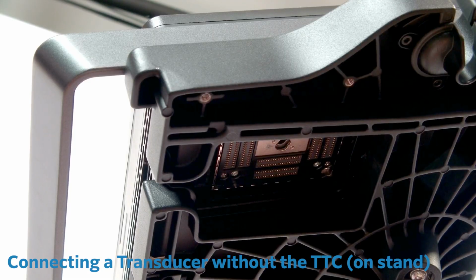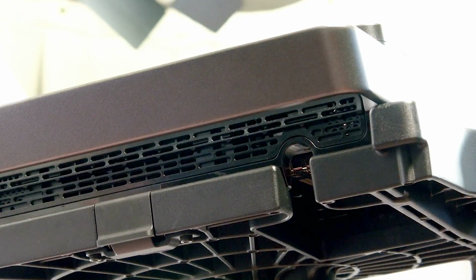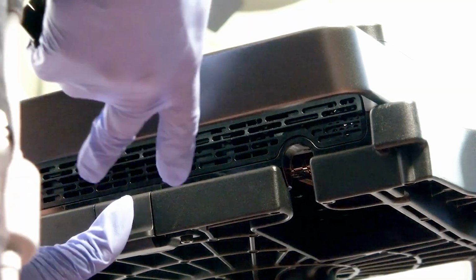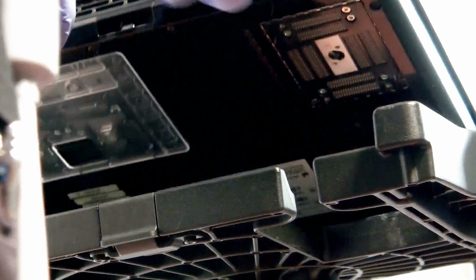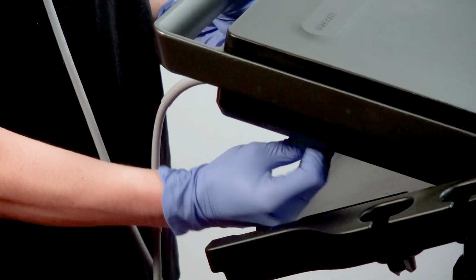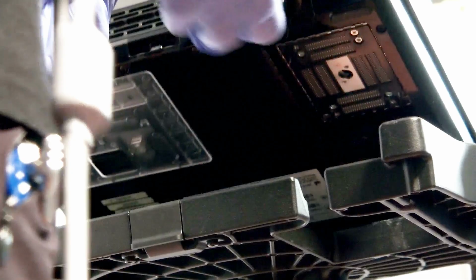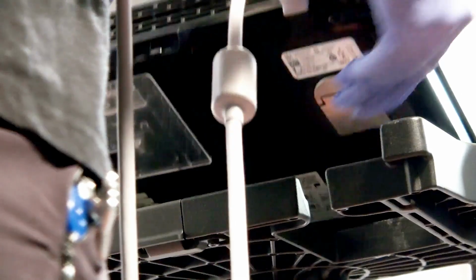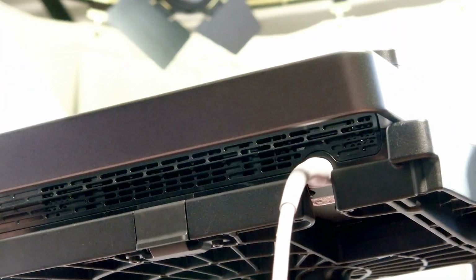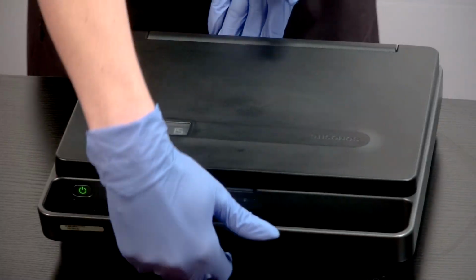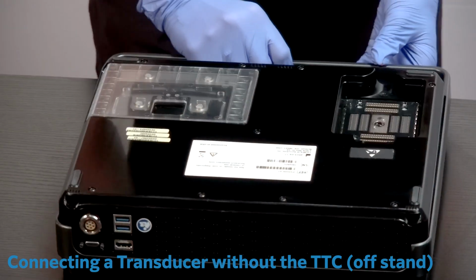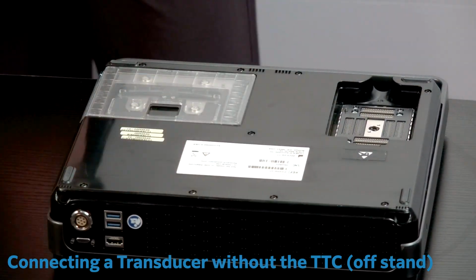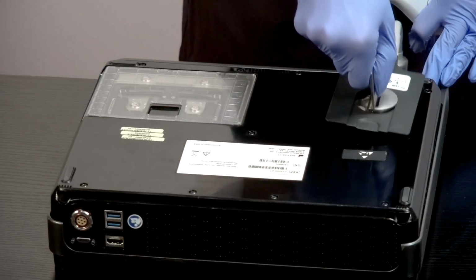To connect a transducer to the system without a TTC while the system is on the stand, release the front of the system from the stand platform by pressing down on the front latch and tilting the system back. Maintain contact of the back of the system to the stand platform. Locate access to the system transducer connector on the right underside of the system. Reach between the system and the stand platform to connect the transducer and follow the same steps as before to secure it. To connect a transducer directly to the system without a stand, turn the system upside down and follow the same steps as before to secure the transducer.